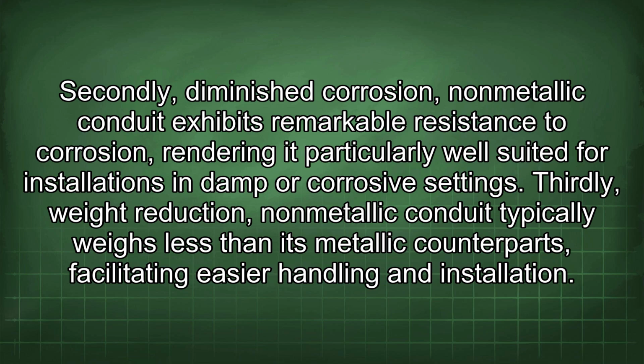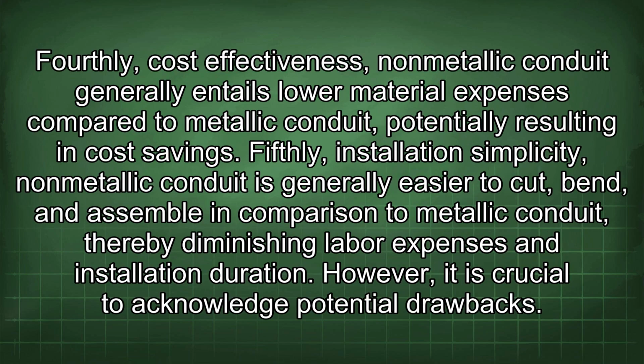Non-metallic conduit typically weighs less than its metallic counterparts, facilitating easier handling and installation. Fourthly, cost-effectiveness. Non-metallic conduit generally entails lower material expenses compared to metallic conduit, potentially resulting in cost savings. Fifthly, installation simplicity. Non-metallic conduit is generally easier to cut, bend, and assemble in comparison to metallic conduit, thereby diminishing labor expenses and installation duration.